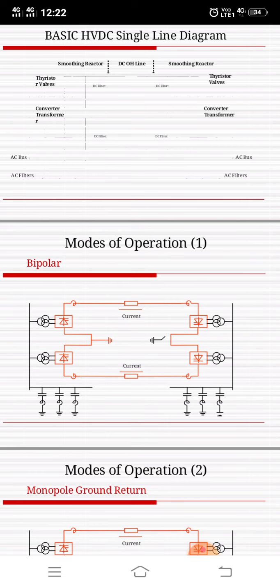The advantages of a bipolar solution over a solution with two monopoles are reduced cost due to one common return path, and lower losses. The main disadvantage is that unavailability of the return path with adjacent components will affect both poles.